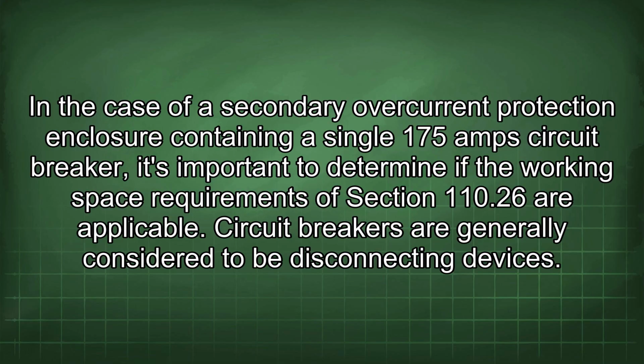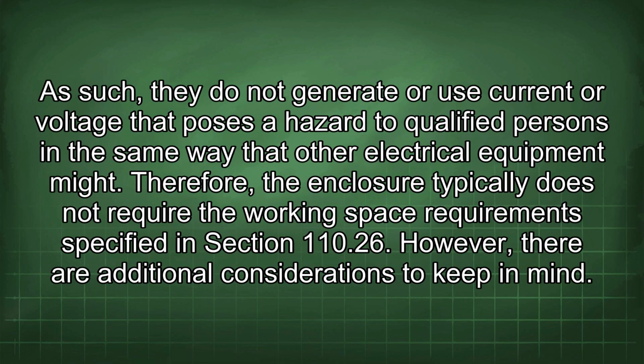Circuit breakers are generally considered to be disconnecting devices. As such, they do not generate or use current or voltage that poses a hazard to qualified persons in the same way that other electrical equipment might. Therefore, the enclosure typically does not require the working space requirements specified in Section 110.26. However, there are additional considerations to keep in mind.